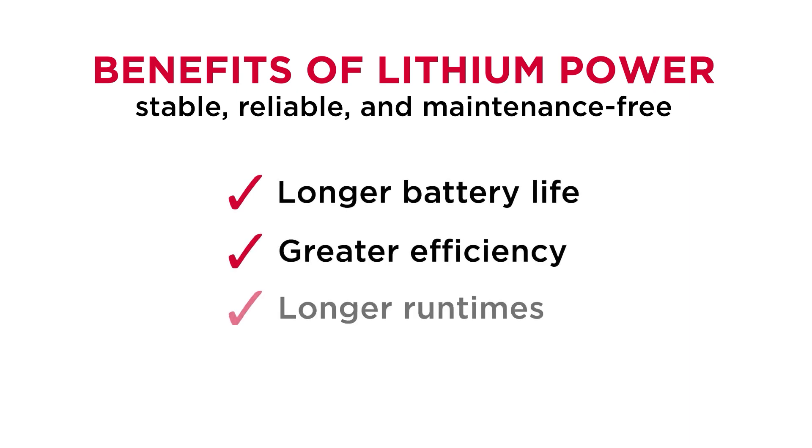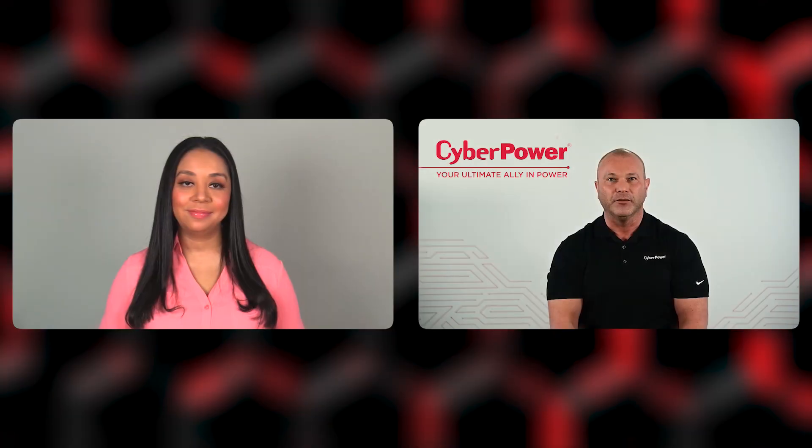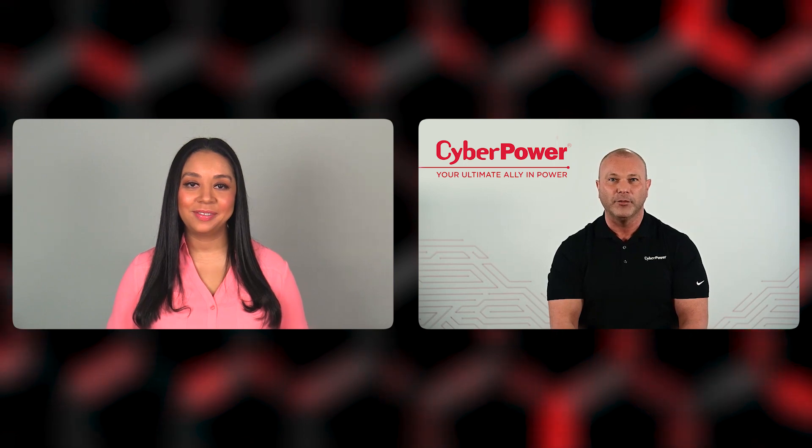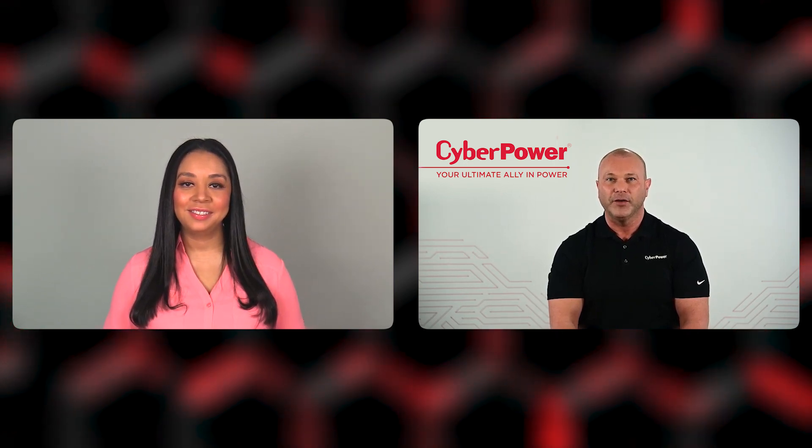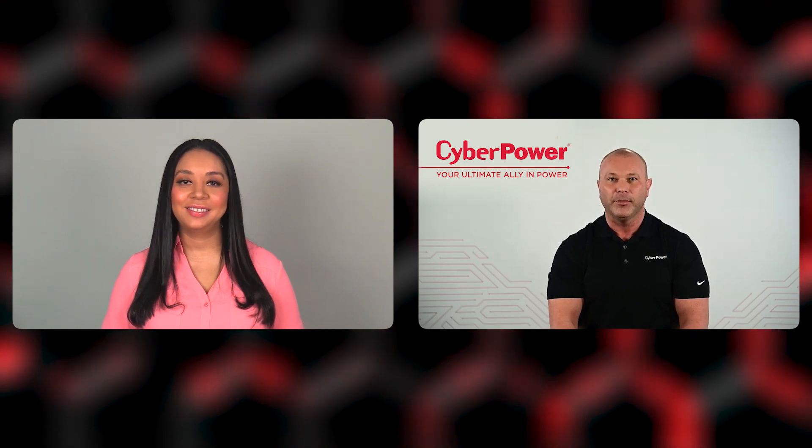This is ideal for longer run times, greater efficiency, longer life, and safety. The cycle life of this battery technology is over four times that of other lithium-ion batteries and can reach 3,000 to 5,000 cycles or more at a greater depth of discharge.